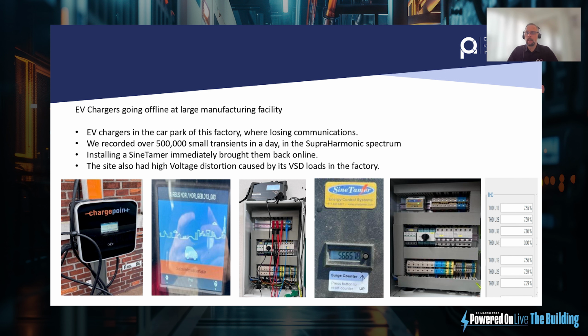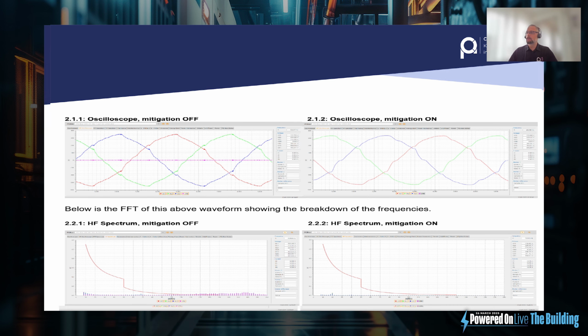They weren't bad, they weren't high, they weren't aggressive values when we measured them with the measuring device, but they were frequent enough to be a problem because of the noise spectrum. So we installed a little SineTamer in there, and immediately all the devices came online and the comms started working and the devices could upload their information. As I said before, the data here is showing you that it wasn't high values, but it was enough to be a disturbance. So on the left bottom corner, you can see the high frequency in pink was 100 kilohertz and above, was affecting the communication cables between the devices that were going out via a router.